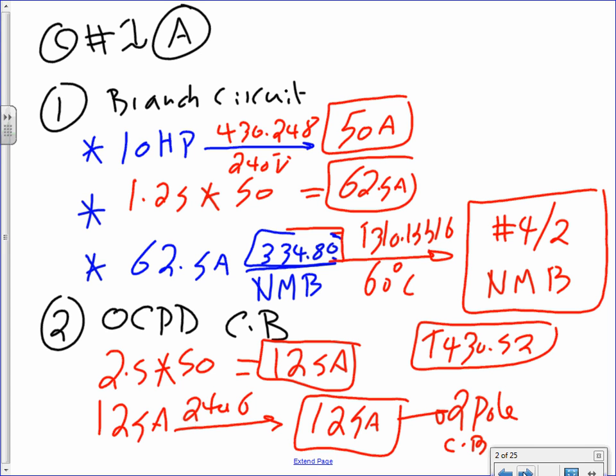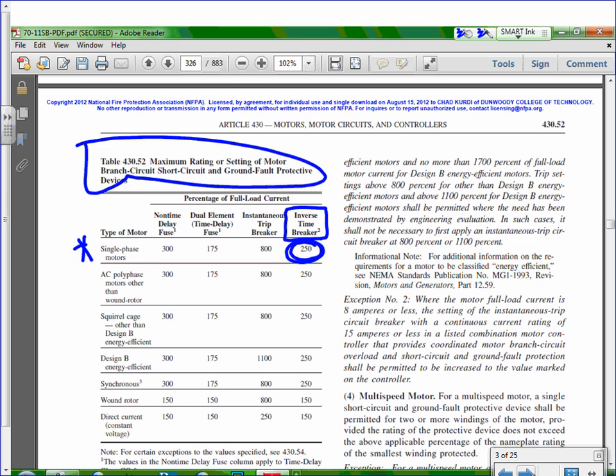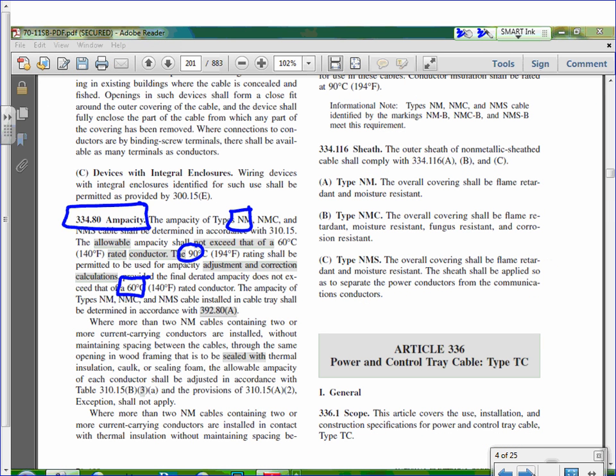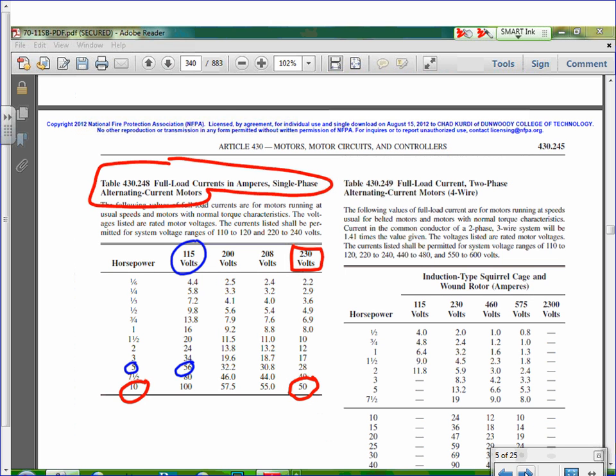Number 2. Cool. Now you can go. Everybody's good? Okay. Now this is what we size. This is where it tells you if you go to an NM cable, it's rated for the 60-degree column. So I have to go to the 60-degree column because that's what it tells me for NM cable. This is the amps. These are just snapshots for a 10 horsepower, 50 amps, showing where we got this information from.